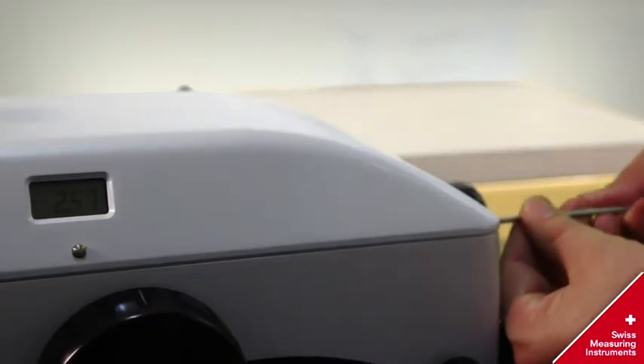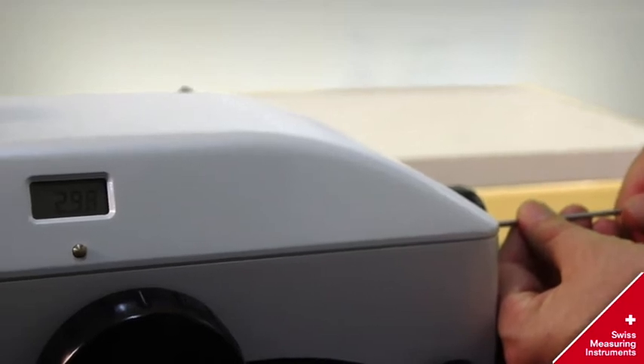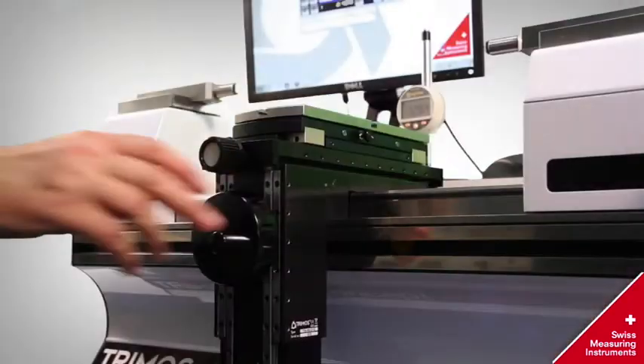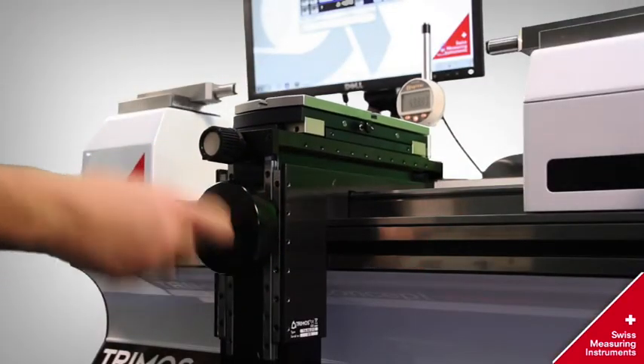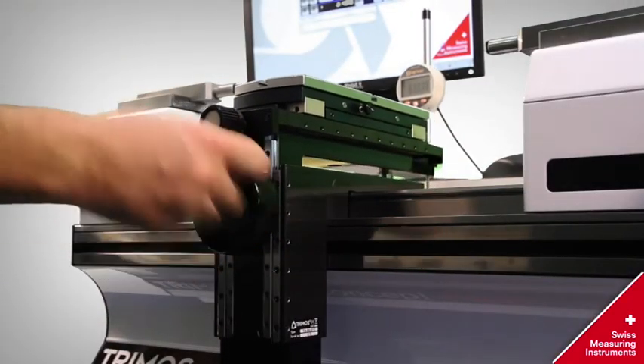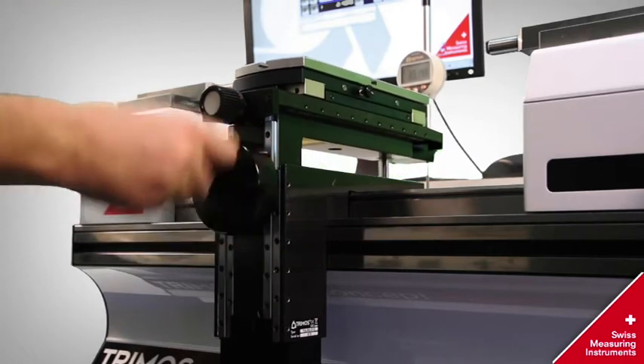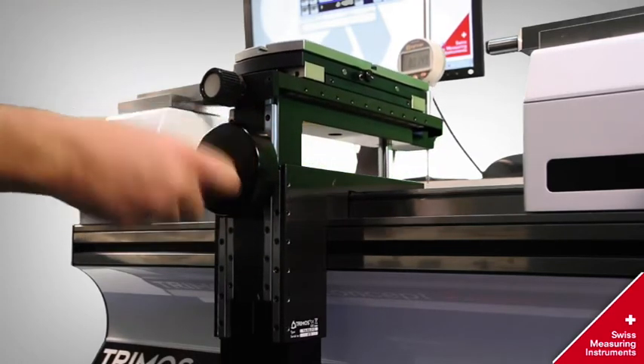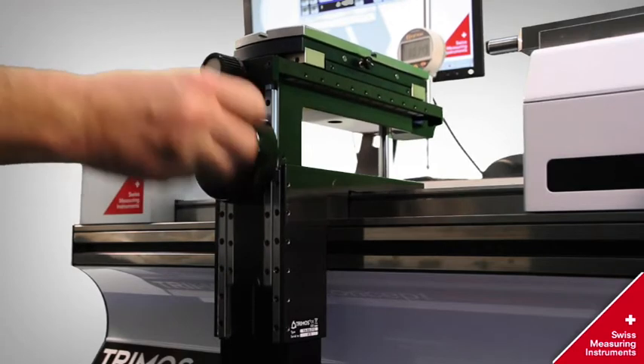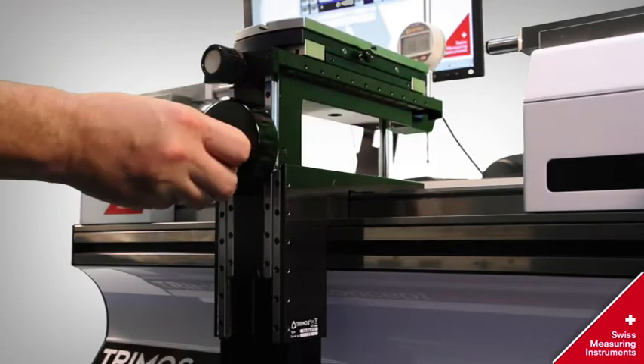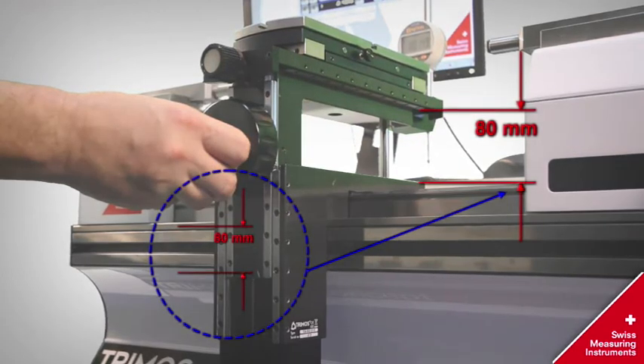Measuring force can be simply adjusted by an Allen key from 0 to 12N and can be seen on the measuring carriage. The universal measuring table offers 5 degrees of liberty. Manual movement of the Z-axis equals the first axis of liberty. Z movement of the universal table allows a measuring range of 80 millimeters.